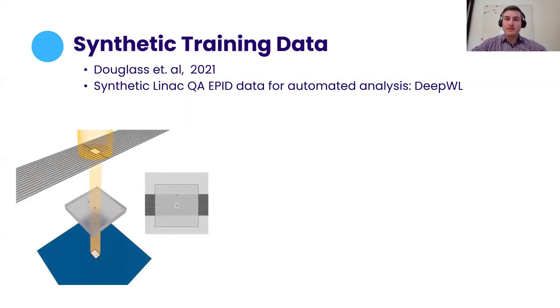In 2021, we also looked at applications of synthetic data for training machine learning models to perform machine QA on our linear accelerators using EPID data. So we modeled a very simple model of a linear accelerator head. We have the MLCs here, we have a radiation field, and we simulated our QA phantom, which is just a perspex block with some ball bearings for scaling and Winston-Lutz isocenter measurements. We also simulated the response of the EPID to this, and this is what it looks like from the beam's eye view. You can see the phantom here, the central ball bearing, and the radiation field defined by the MLC leaves.